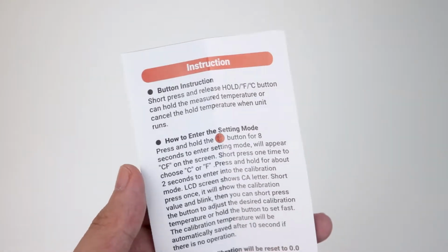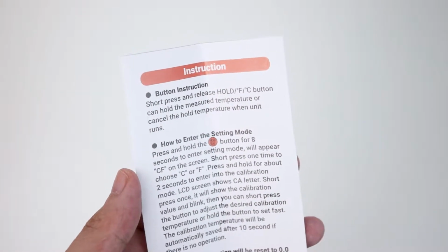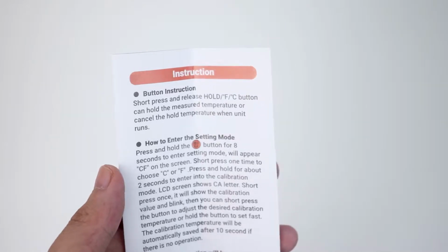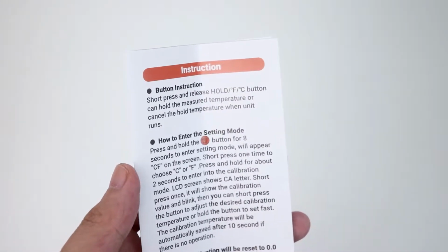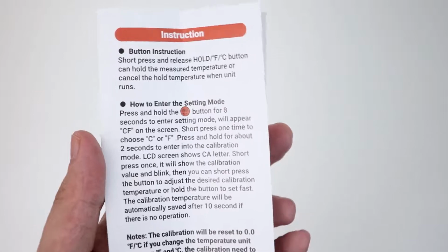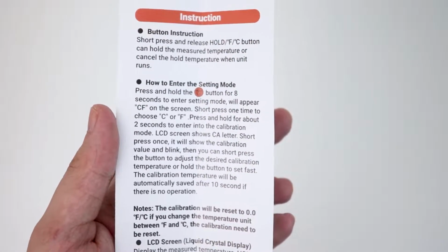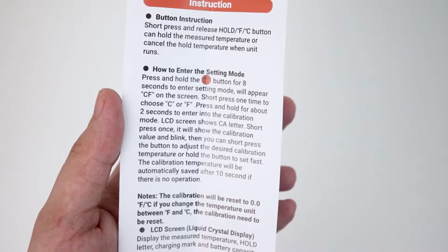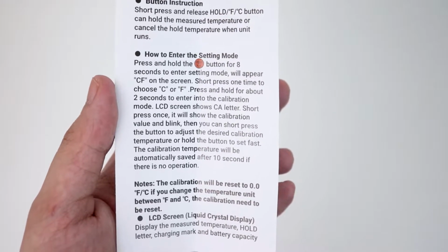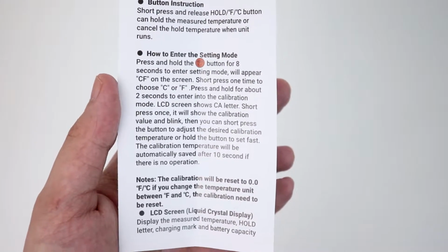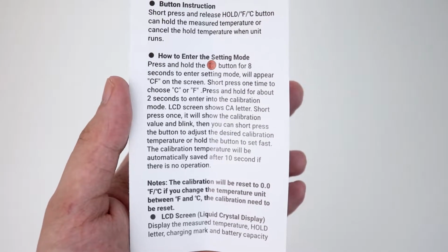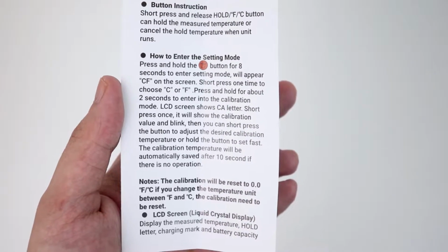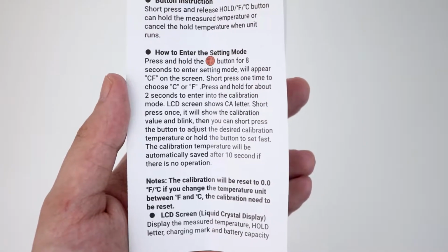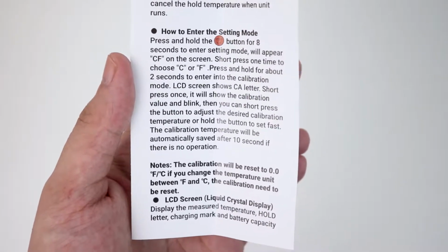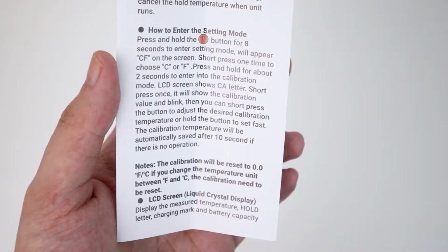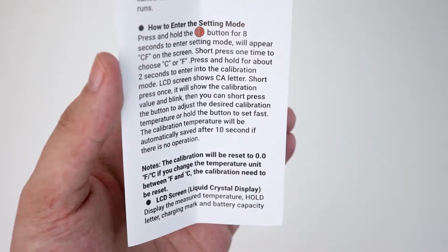From the sound of the product, it sounds quite rigid and the build quality is really good, intact, even though it's made of plastic. Here we have the instructions for that one button we have in the front of the device. If you short press it, it will hold the temperature readout for you to properly read it. Once you hold it for 8 seconds, you can change it from Celsius to Fahrenheit. And if you hold for an additional 2 seconds, you will enter the calibration mode. And just follow these calibration instructions until it resets to 0. And that's what we are looking for.